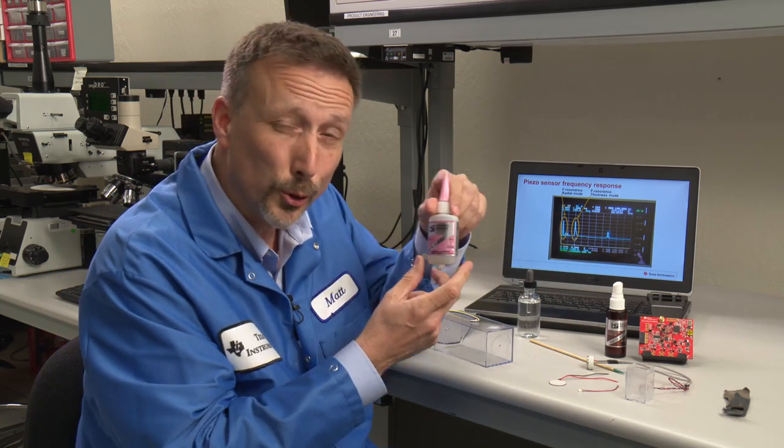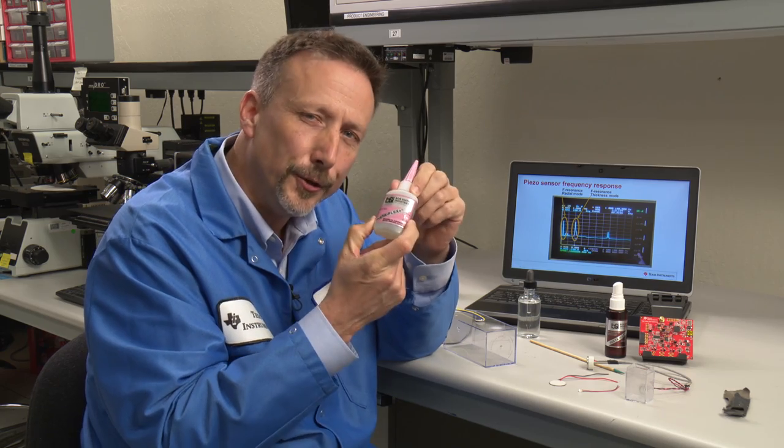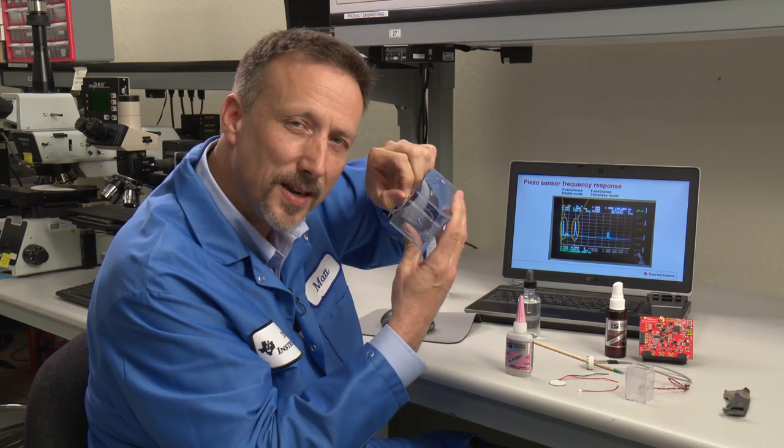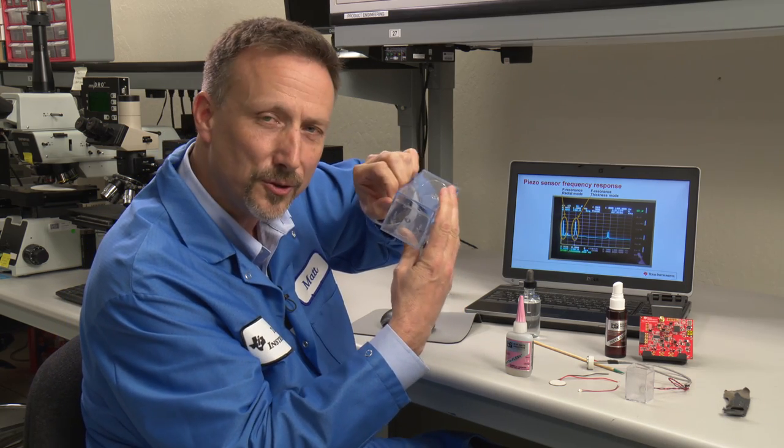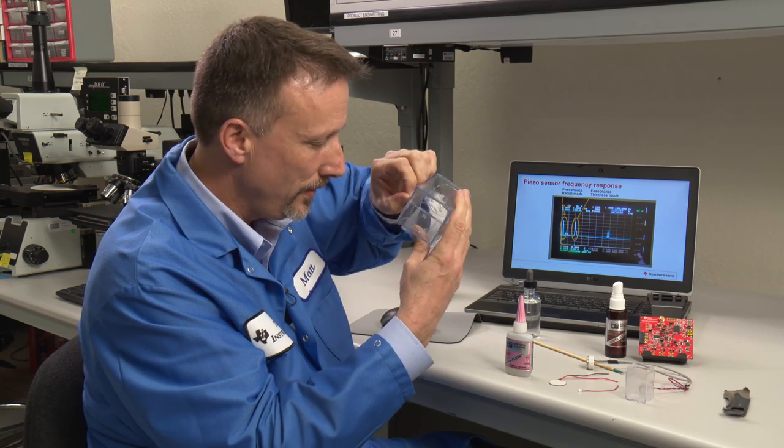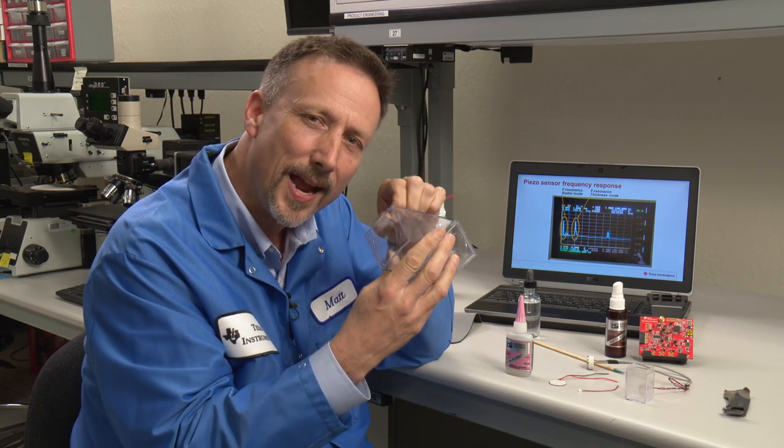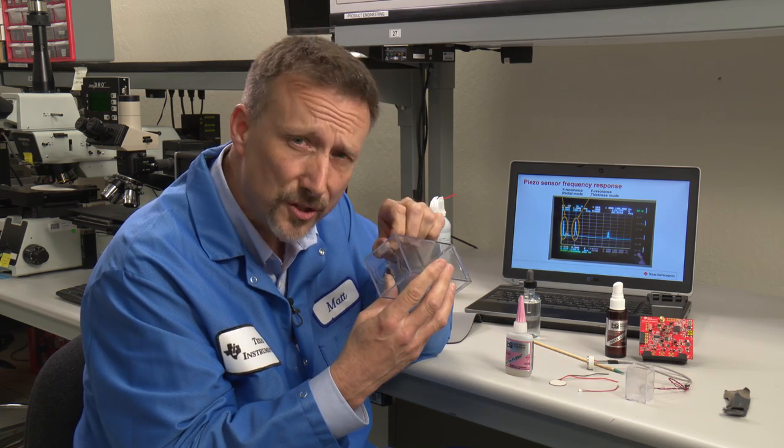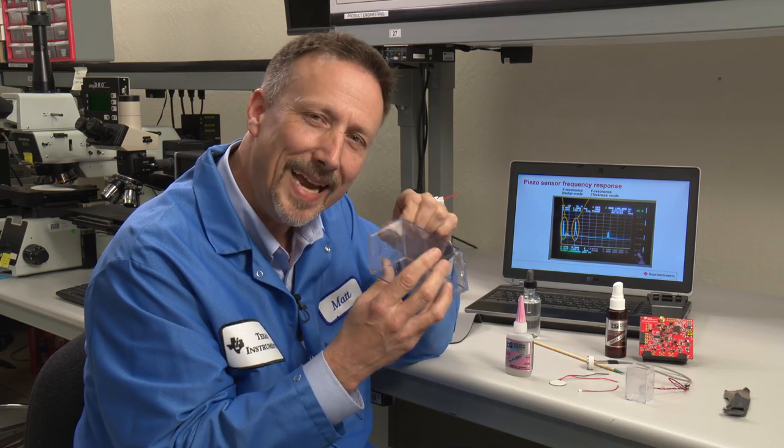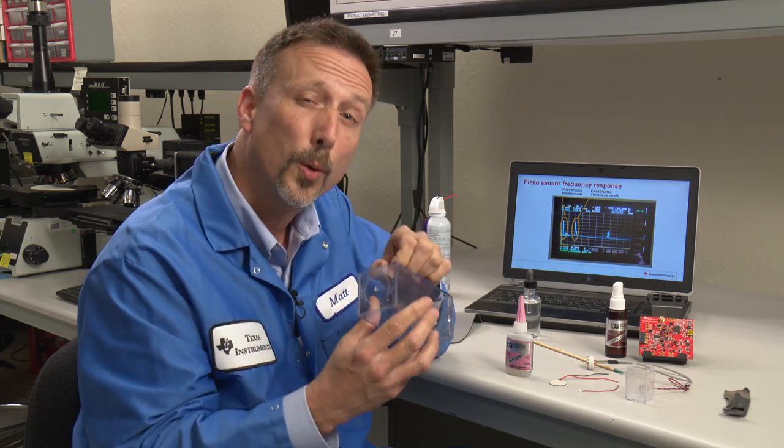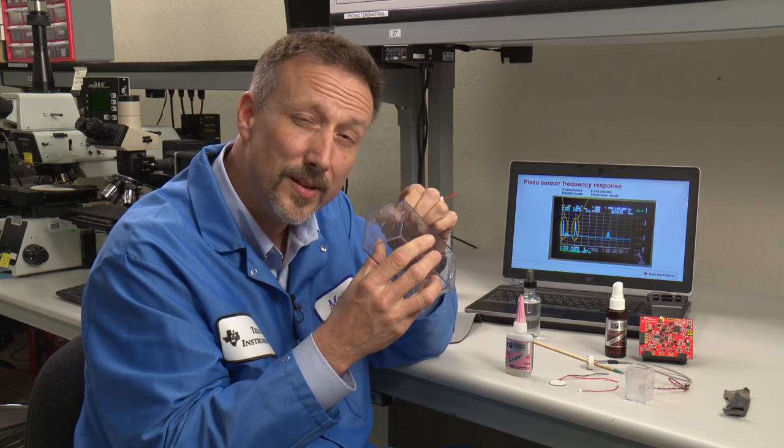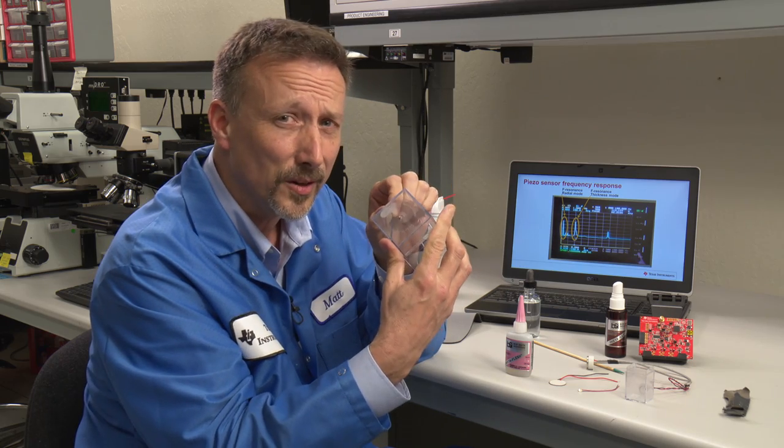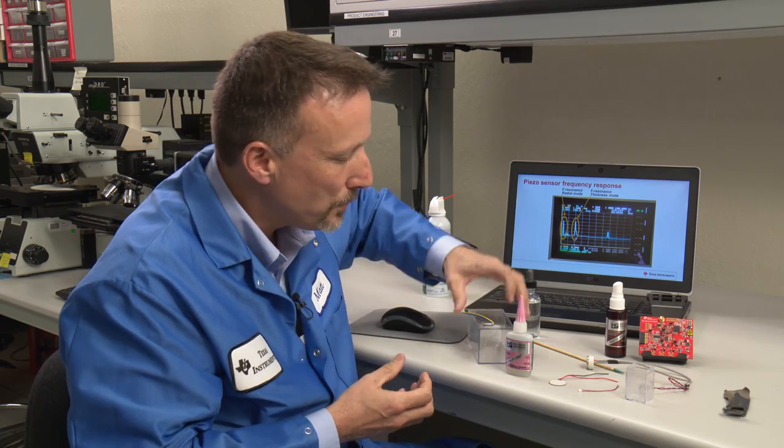Let's talk a little bit about glue. What does this glue need to do? The purpose of this glue is to maximize the connection between this transducer and the wall of my container. I can't afford to have an elastic glue because an elastic glue acts like an acoustic resistor. It dampens down any energy going into the container or being the echo received.